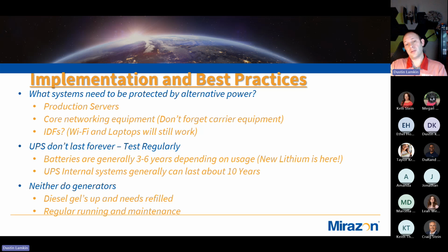Also on the UPSs, one thing to know is the UPS doesn't know when its batteries are bad, you actually have to apply a load. It'll see good voltage the whole time, but if you're not putting a load on it, the UPS might say it's fine, and then when it actually has to carry a load, it just shuts off completely. So that's something we definitely want to test on a regular basis.